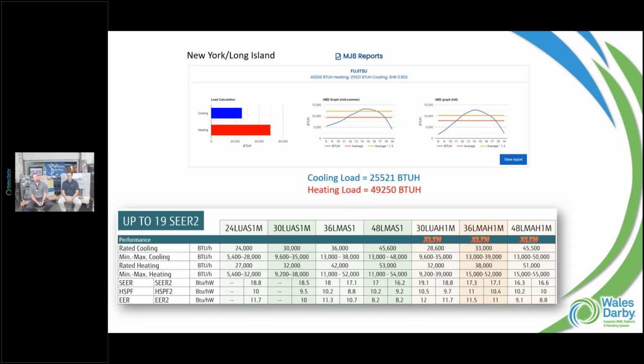But when you're chasing rebates and stuff like that, and maybe sizing out of the catalog - I know you love talking about that. So I put this little spec sheet here out of the catalog where you see a lot of numbers: your rated numbers, your minimum and max cooling, minimum and max heating. And if we are doing the right thing by doing a load calc, we can still get ourselves in trouble just by looking at the catalog and picking a piece of equipment. You really got to get into the back end, into what we call our design and technical manual, where I'm going to pull up a couple charts to walk through some of that stuff. Stop me whenever you want.